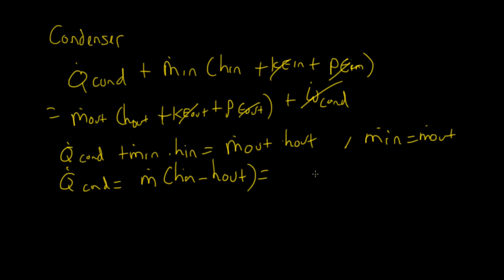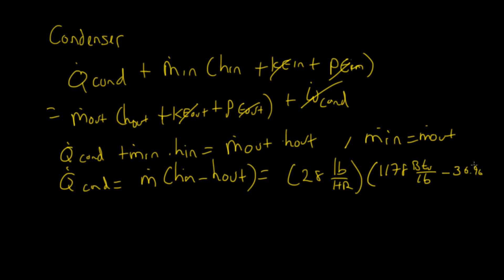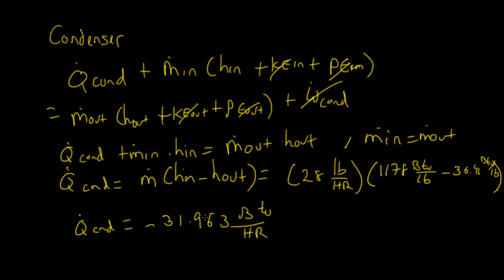Plugging in the numbers: mass flow rate is 28 pounds per hour, H_in is 1178 BTU per pound, H_out is 36.46 BTU per pound. This gives Q_condenser equal to minus 31,963 BTU per hour. It's negative because the heat is coming out — exactly what we should be seeing.